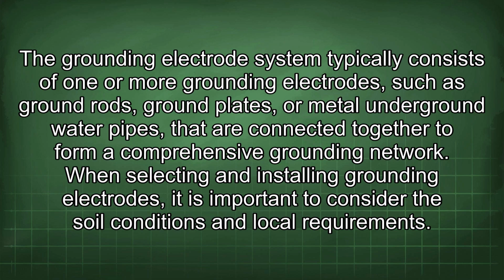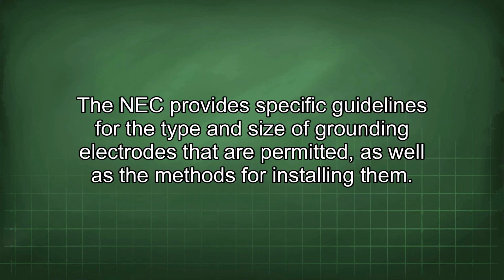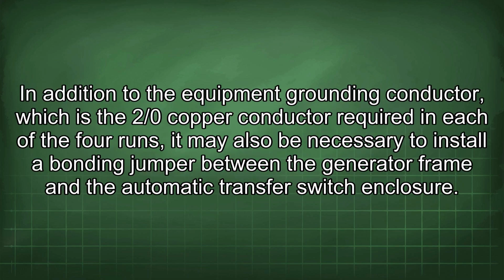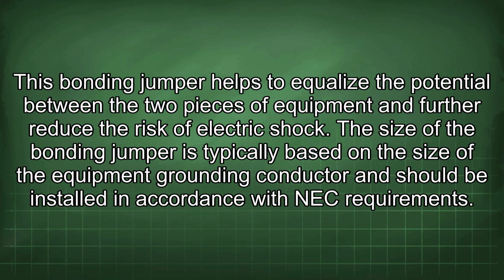When selecting and installing grounding electrodes, it is important to consider the soil conditions and local requirements. The NEC provides specific guidelines for the type and size of grounding electrodes that are permitted, as well as the methods for installing them. In addition to the equipment grounding conductor, which is the 2/0 copper conductor required in each of the 4 runs, it may also be necessary to install a bonding jumper between the generator frame and the automatic transfer switch enclosure. This bonding jumper helps to equalize the potential between the 2 pieces of equipment and further reduce the risk of electric shock.